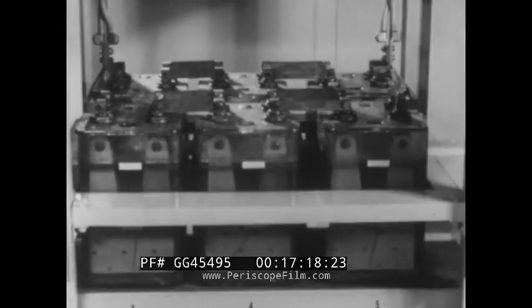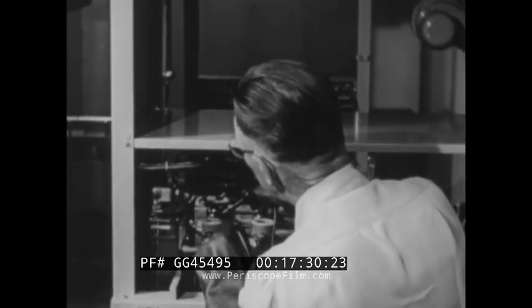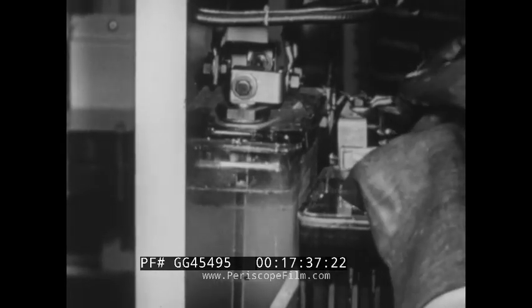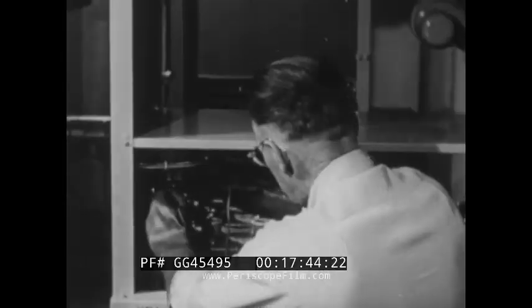The value of the counter-cell voltage varies slightly with the load, as is the case with the storage battery. The gas formed in the counter-EMF cell is also very explosive. A check should be made of the voltage across the counter-EMF cell with it in the discharge circuit, when the cell readings of the battery are taken. When the voltage drop increases to 2.6 volts, the solution should be changed to prevent damage to the cell.